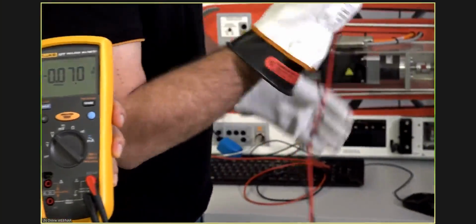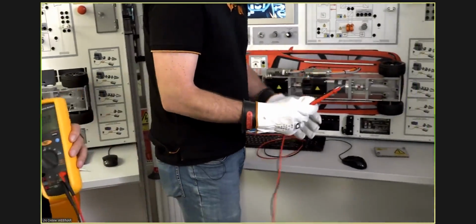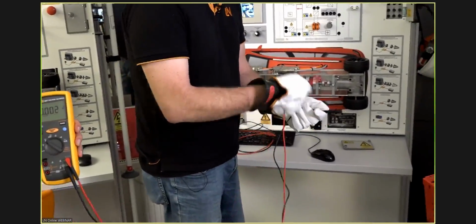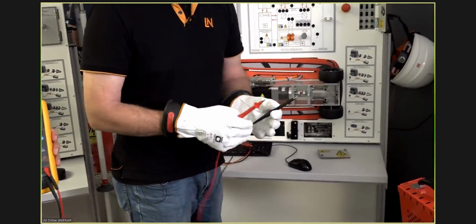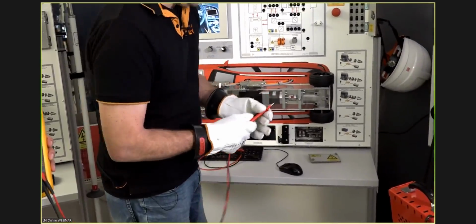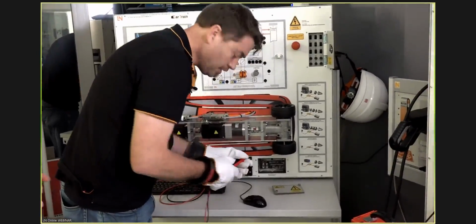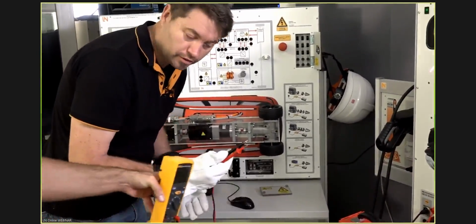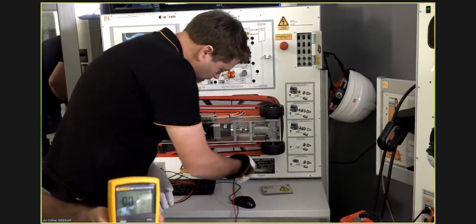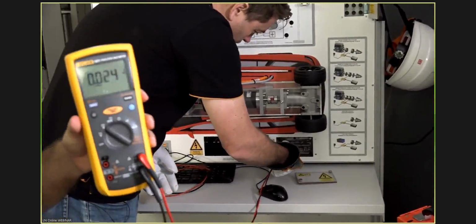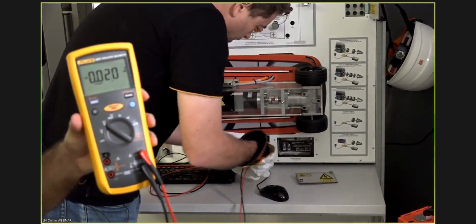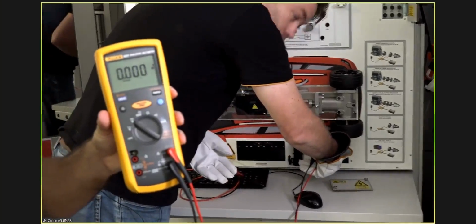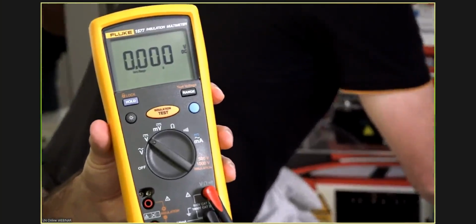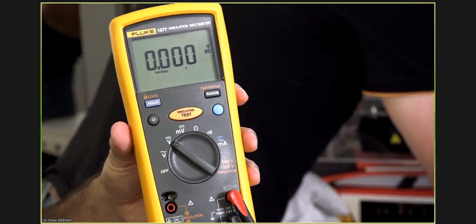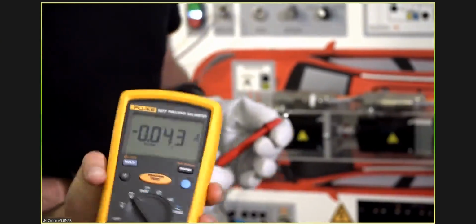Now I'm using a one-hand rule. If we use two hands and make a mistake, we can become part of the circuit, if we make mistakes or even when the gloves have a problem that you haven't seen. Exactly. So go down and measure at the high voltage point and make sure there's 0 volts. Sometimes you might get 1 or 2 volts, that's okay, as long as you're not getting the full voltage.